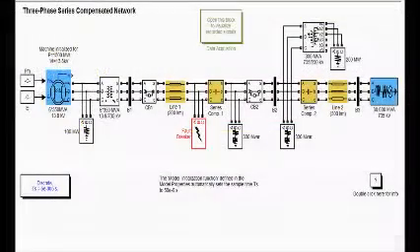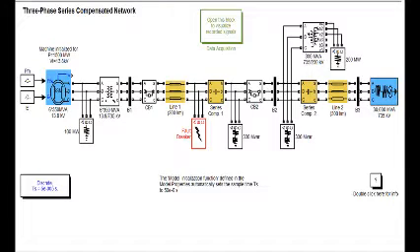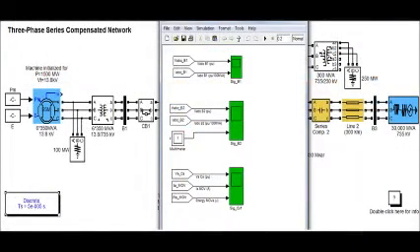In order to increase the transmission capacity, each line is series compensated by capacitors representing 40% of the line reactance. Both lines are also shunt compensated by a 330 MVAR shunt reactance. These shunt and series compensation equipments are located at the B2 substation, where a 300 MVA 735/230 kilovolt transformer with a 25 kilovolt tertiary winding feeds a 230 kilovolt 250 megawatt load.